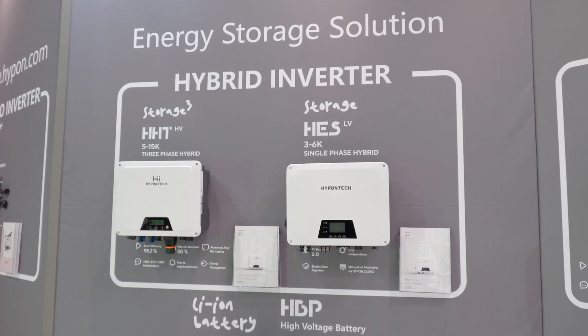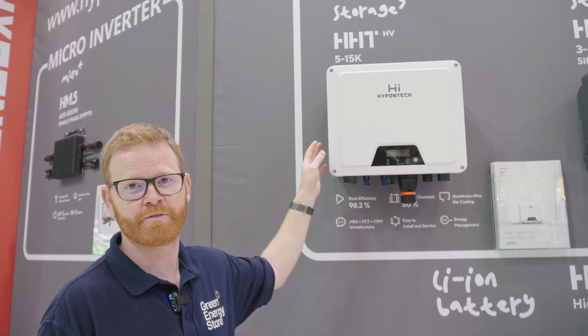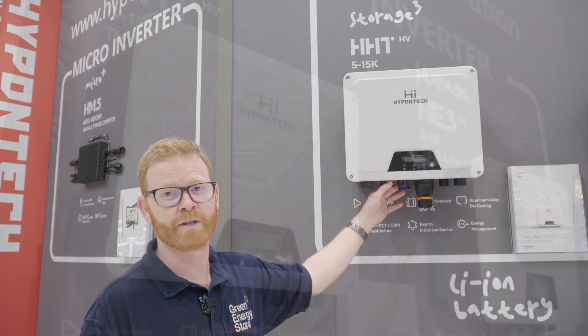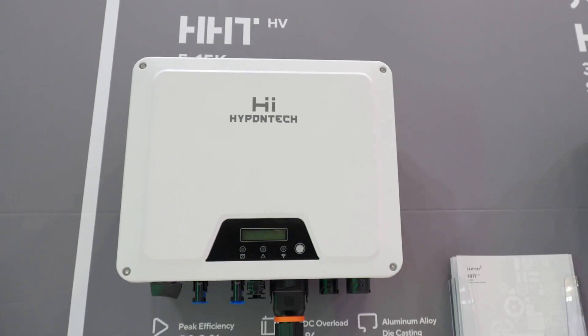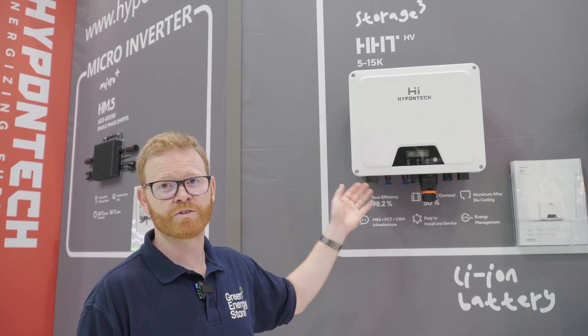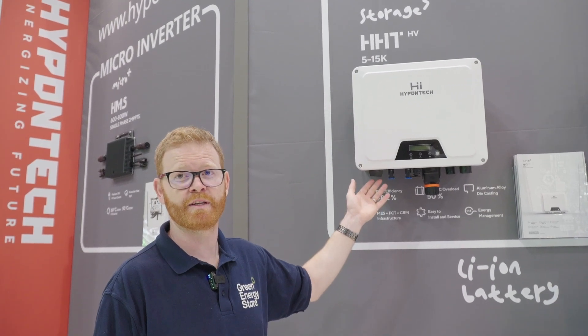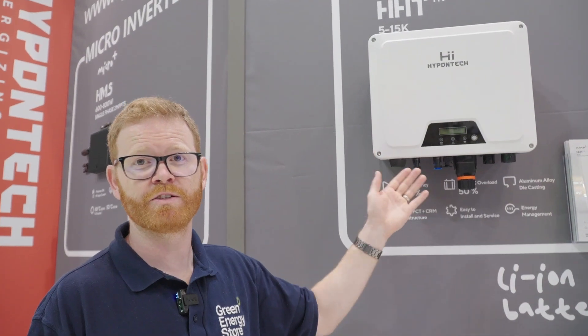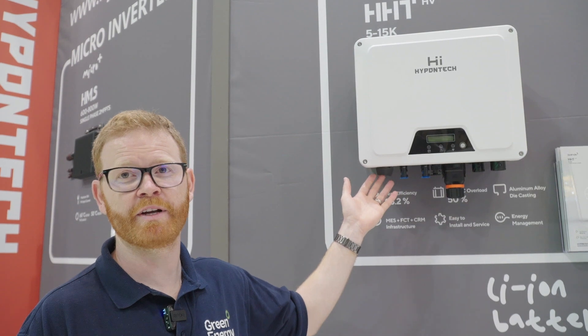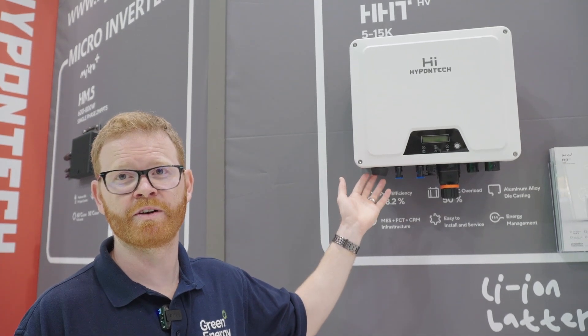These are the Hypontech 3-phase and single-phase hybrid inverters. The 3-phase range goes from 5 kilowatt up to 15 kilowatt. It is a high-voltage inverter with two built-in MPPTs that can take up to one and a half times the input PV power. The Hypontech Cloud connects wirelessly via a Wi-Fi dongle, with Bluetooth also built in, allowing all settings to be controlled remotely via the app — preventing the installer from having to return to site.